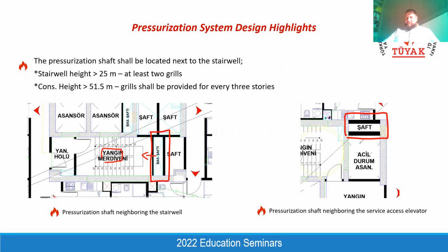When you have a fire service access elevator within the building, you need to provide a pressurization shaft for this elevator well as well. If you forget to provide it, they will require a hard duct system at the corner of the elevator well, and it is not accepted by the guys who check and approve the elevator. Inspectors are not accepting this kind of hard-ducted system. That's why having a pressurization shaft just next to the service access elevator well is really important and should be designed from the beginning of the project.